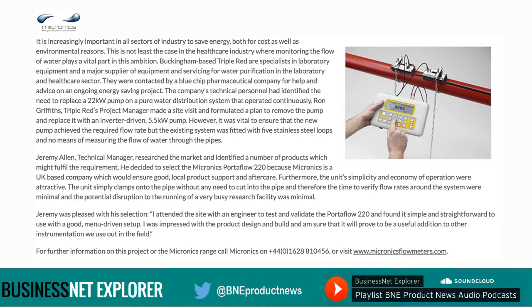The company's technical personnel had identified the need to replace a 22 kilowatt pump on a pure water distribution system that operated continuously. Ron Griffiths, Triple Red's project manager, made a site visit and formulated a plan to remove the pump and replace it with an inverter-driven 5.5 kilowatt pump. However, it was vital to ensure that the new pump achieved the required flow rate, but the existing system was fitted with five stainless steel loops and no means of measuring the flow of water through the pipes. Jeremy Allen, technical manager, researched the market and identified a number of products which might fulfil the requirement. He decided to select Micronics Portaflow 220, because Micronix is a UK-based company which would ensure good local product support and aftercare. Furthermore, the unit's simplicity and economy of operation were attractive.